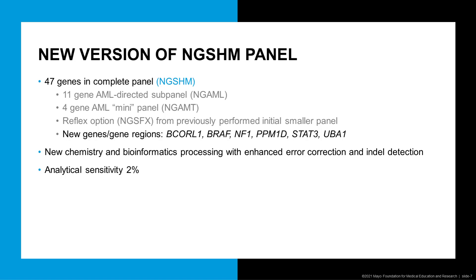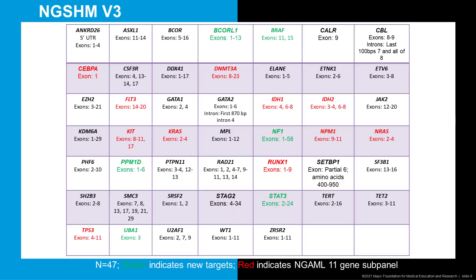The new NGSHM panel includes an update to the chemistry — it's actually a new type of chemistry. The bioinformatics processing is also updated and upgraded with a number of important features, including enhanced error correction, a contamination module for high-throughput sequencing with multiple samples, and improvements for indel detection. The analytical sensitivity has improved slightly to 2%. In tabular format, this is showing the new panel: the red font genes are the subpanel NGAML genes, and the green font genes are the new ones that have been added.